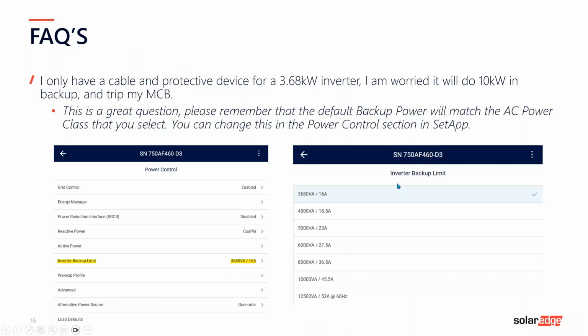Then you have your default limit. So default limit is this, but you can get it to do any one of these. So I can have my 3 kilowatt giving me 10 kilowatt of backup as long as I have enough battery and enough PV, so 2 batteries. Please remember, the Home Hub inverter, if you have 2 batteries, will give you 10 kilowatts on a 10 kilowatt inverter. You'll get 10 kilowatts out of those batteries.